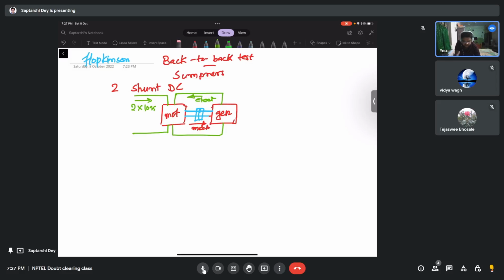So suppose these machines are, say, 50 kilowatt machines. Both of them are, let us say, 90% efficient, right? So if you have 50 kilowatt machines with 90% efficiency, and you do not do the Hopkinson test, and just simply full load the machine and test, what will you be drawing from the supply? Input is 50 by 0.9, around 55.